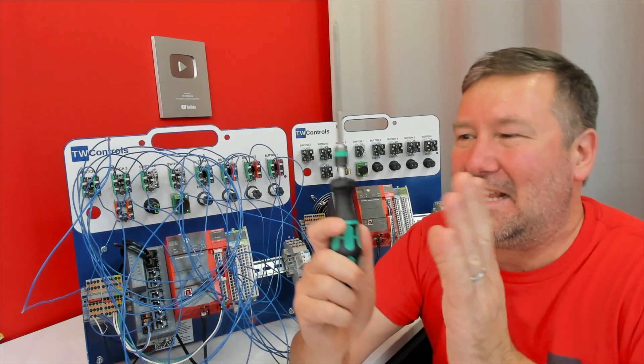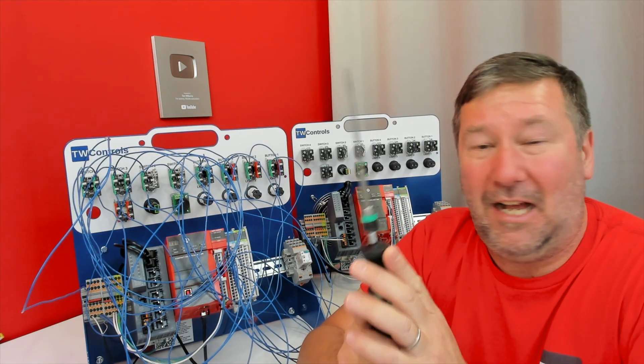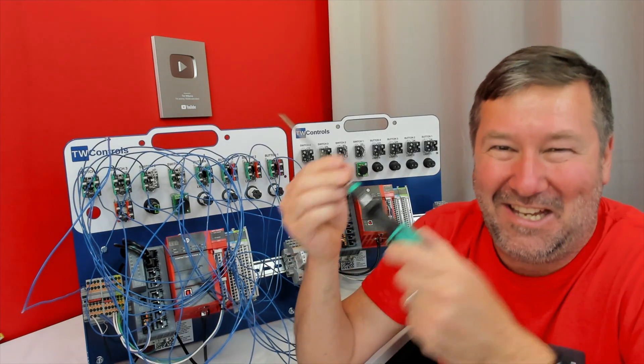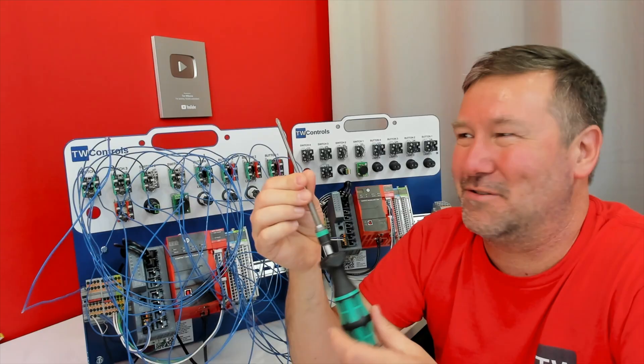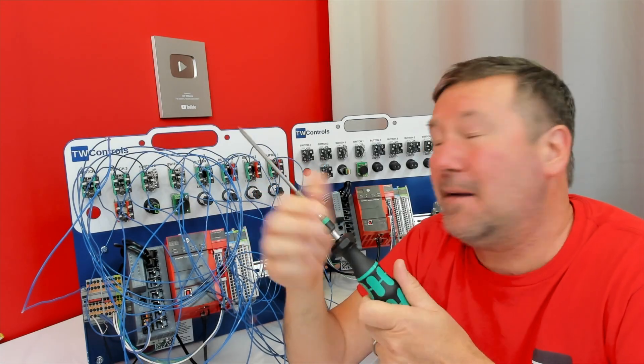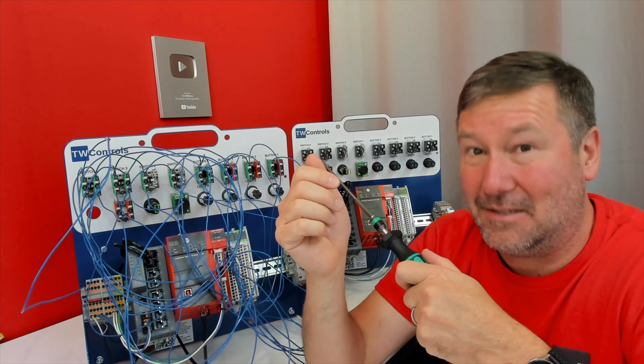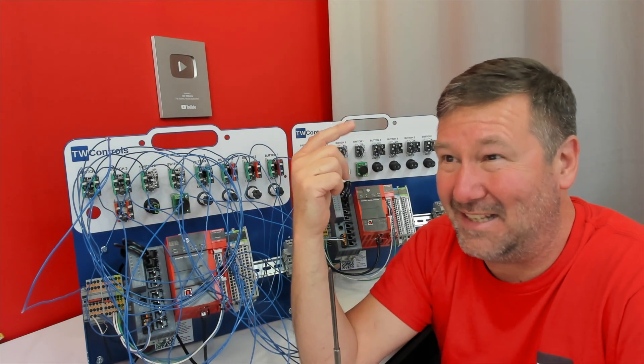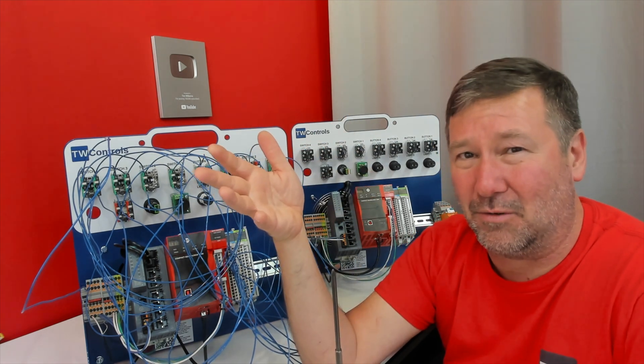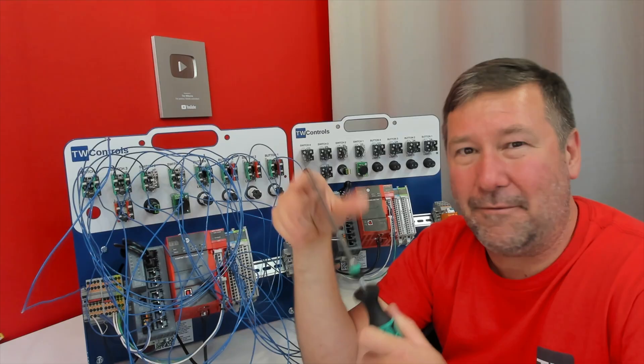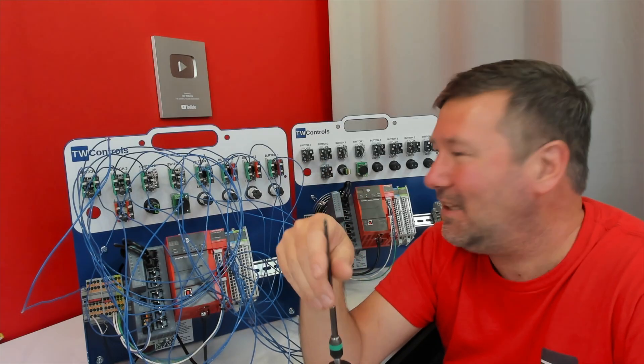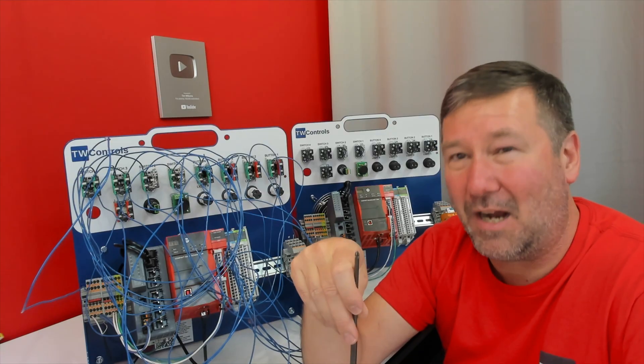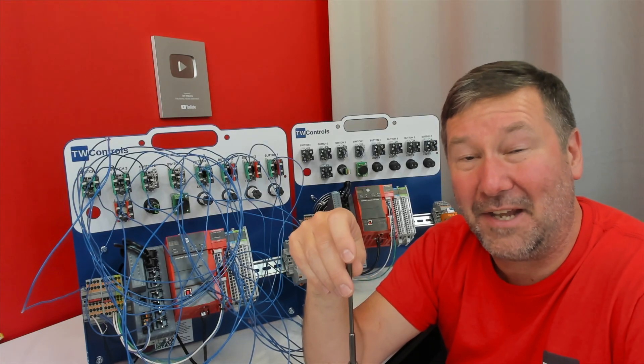Now, I don't think I can say that gets us out of having a calibrated screwdriver. Because if you're a UL panel shop, you're occasionally going to have a screw terminal. So we don't get past that, but because I do torque these so often, I knew the torque specs in my head. So we also didn't have to look up the torque specs. We didn't have a chance for a mistake. I think overall that this is not only a time saver, it's probably going to increase the quality of our panels.